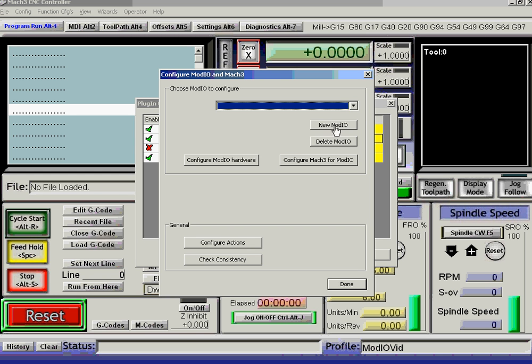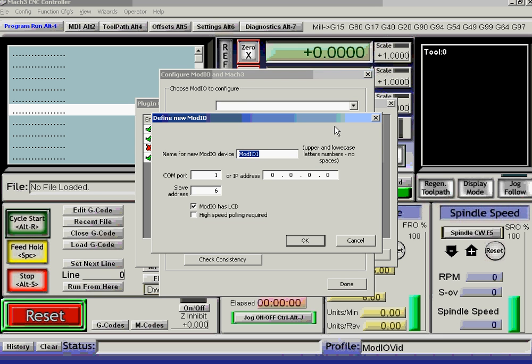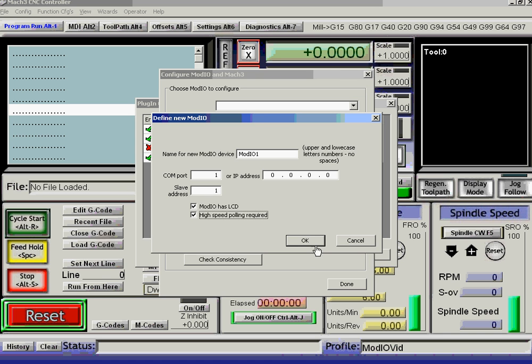So let's define the first one. You can call them what you like. I find it convenient to call it numbered, with the same as the slave port address. So it's on COM port 1, and the new ModIO, I've got the switch set to 1. It's got an LCD, and I'm going to use high-speed polling.